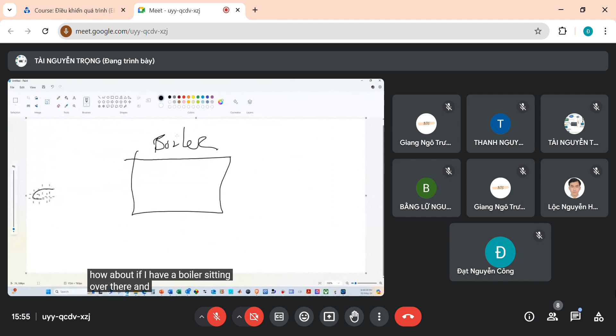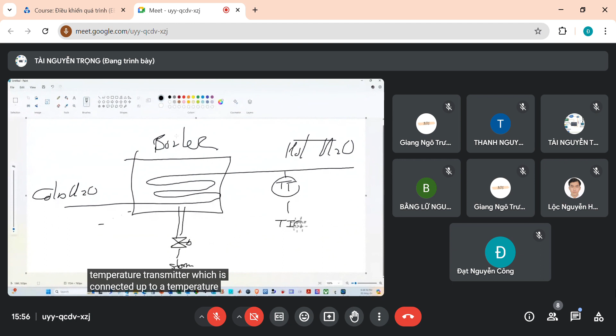Some of you might even hear people talk in terms of a cascade control. In the case of a cascade control, I've usually got one controller built into another. How about if I have a boiler over there, and I have cold water coming into the boiler, and I would like to have hot water coming out of the boiler. I can bring in steam. That steam is going to go through a control valve into my boiler, and I can use that to control the flow. I've got a temperature transmitter, which is connected up to a temperature indicator and a controller with a set point, and that is going to operate my steam valve over there.